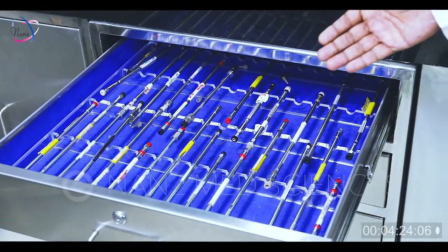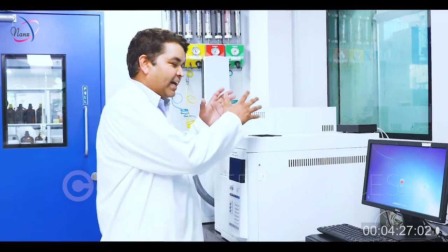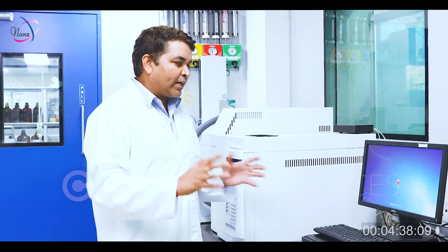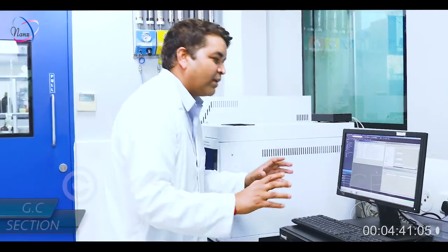The instruments are covered by the required AMC with the supplier. The column management ensures inventory, verification, performance, usage, and decision for their destruction. The QC laboratory is also facilitated with 2 Agilent gas chromatographic systems. The system is also fully validated to meet all the requirements of 21 CFR Part 11. Data management and audit trail are activated as per the compliance requirement. Calibration of the instrument is done in-house through the respective SOP, but AMC is ensured to check the periodic health and troubleshooting of the system.